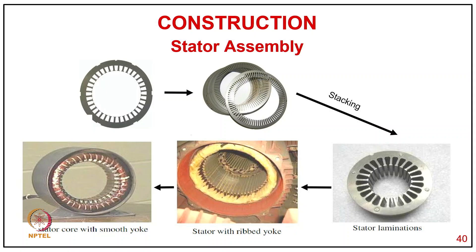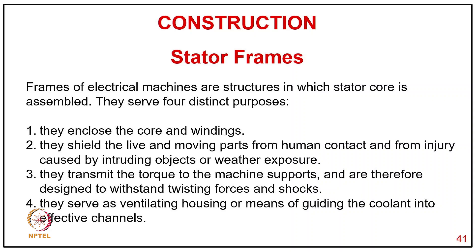The stator frame is the structure in which the stator core is assembled. It serves four distinct purposes: enclosing the core and winding; sealing live and moving parts from human contact, injury from introduced objects, or weather exposure; transmitting torque to machine supports to withstand twisting forces; and serving as a ventilating housing or means of guiding the coolant into effective channels.